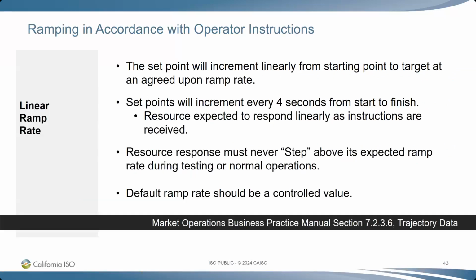Ramping is another important thing to be considered when you're following operating instructions. For any kind of instructions received, the set point is going to increment linearly from the starting point to target at an agreed upon rate. This could be during testing, but it's also when your resource is getting an award. Your set points are going to increment every 4 seconds from start to finish, and a resource is expected to respond linearly as instructions are received. So resource response - you're not supposed to step above what the expected ramp rate is during testing or normal operations. Again, those ramp rates are listed according to your master file, what your capabilities are.